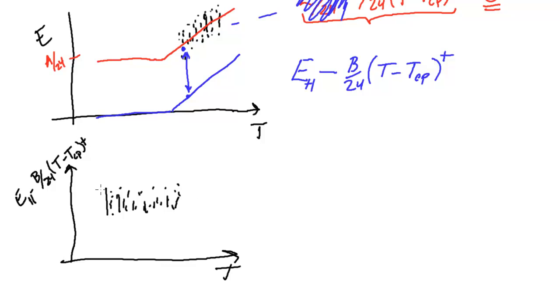This is E_hourly minus B divided by 24, T minus T. And now, we can go ahead and we can say, okay, now let's take this data set and let's use other predictors that we know can maybe help us out. So, if we took this variable and instead of plotting against T, we plotted it against, let's say, some measure of occupancy. So, when occupants are there, you might end up getting something, this would be obviously a very ideal case, but something very linear with regards to occupancy, where when this residual is high, so this energy use versus this model is high, that means perhaps there's a lot of internal load at that moment, at that hour.